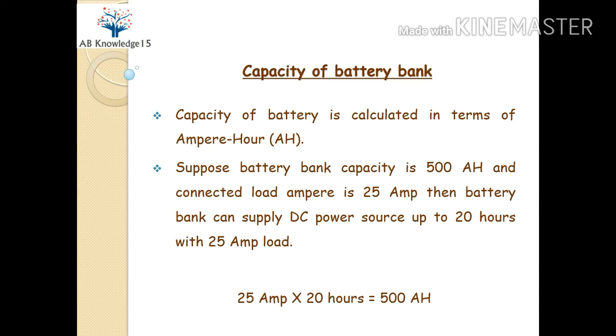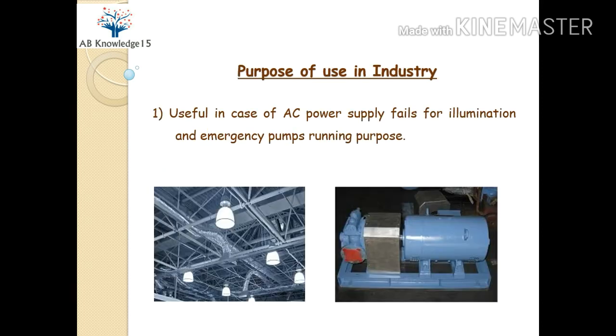Then the battery can supply DC power for up to 20 hours with a 25 ampere load. It is a simple calculation: 25 amperes multiplied by 20 hours equals 500 ampere hours. By this calculation you can determine how many hours your battery bank will supply DC power at a given ampere loading. This is the capacity of the battery bank.